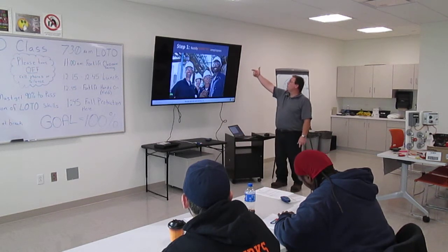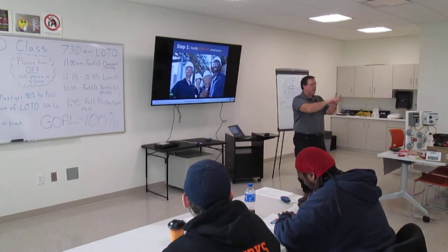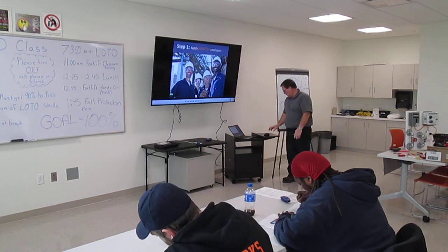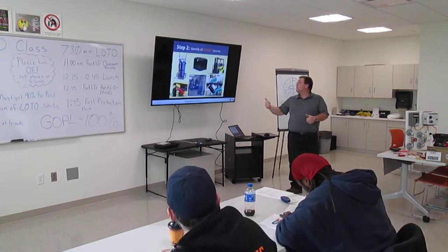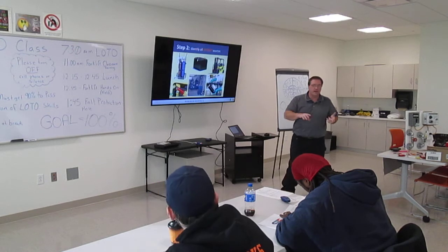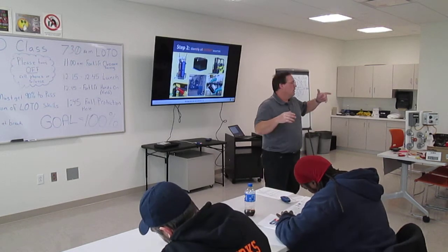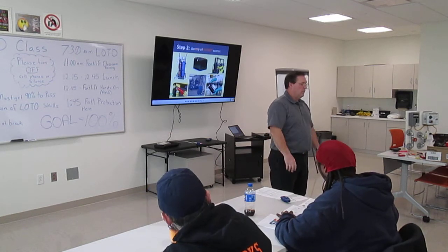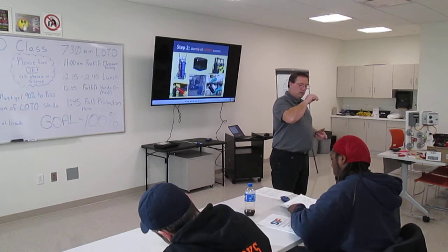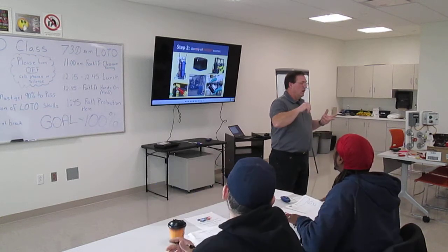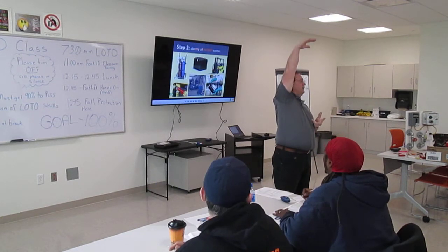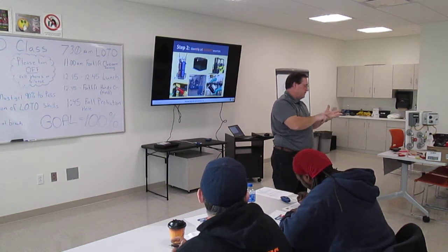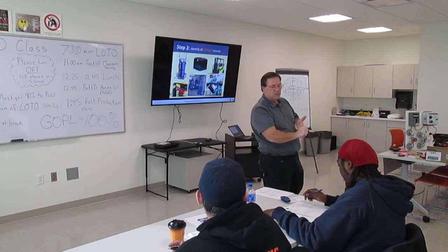Okay. Step one, we notify affected employees. The employees work in the area, may operate the equipment, might be your supervisor, might be absolutely nobody. Step two, we're going to identify all our energy sources. This is when you guys have to use your experience, your knowledge, and say, hey, tray former, box machine, in the box shop. There's an electrical disconnect, there's an air line, and it goes up here and stays there until something else happens. So I got electrical, I got pneumatics, and I got potential energy.